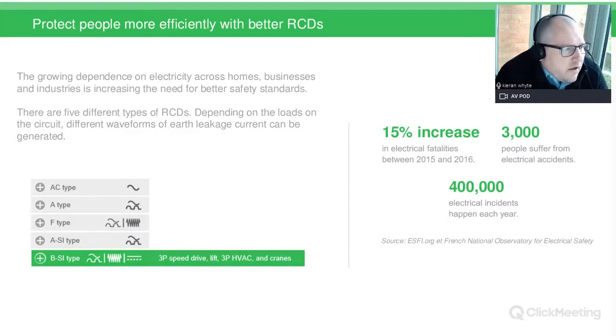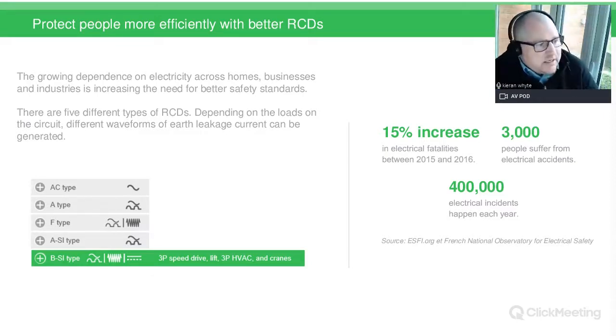Okay, I thought it was a very good video there showing the different RCDs and how the effect of DC can affect their operation. So to protect people more efficiently with RCDs, we need to make sure we select the correct type. AC is traditional, for more resistive loads. A type for up to 6 milliamp. F type as the milliamp on the DC load increases, but for the full protection, look at the SI type in the Schneider world, or the B type.